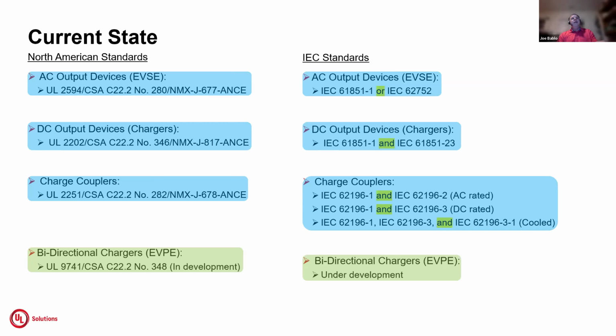When I speak about them today, I'm just going to reference the UL number for convenience, but it's UL 2594 for AC devices, which correlates to the IEC 61851 or IEC 62752 standard. I say correlate because they're not exactly harmonized, but they do use the same safety concepts, even though formatting or approach may be different.